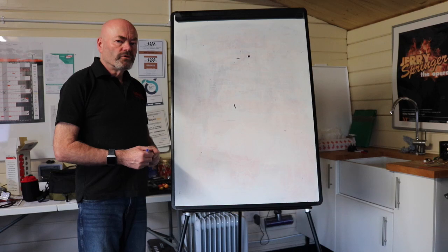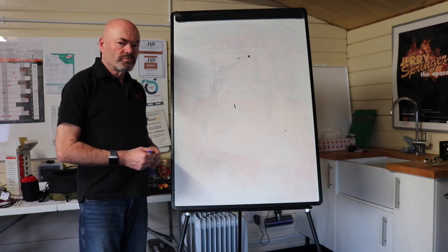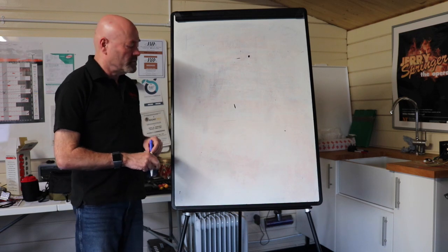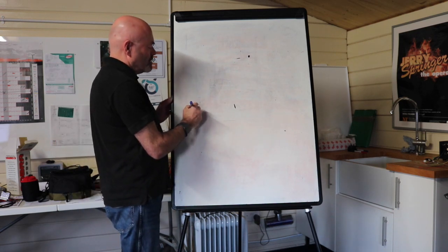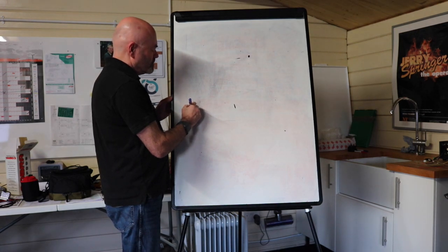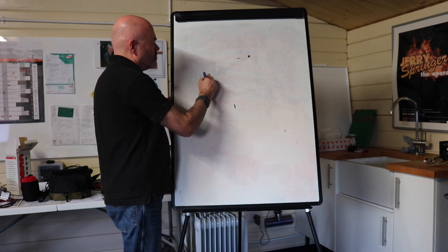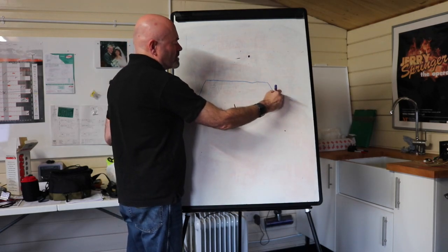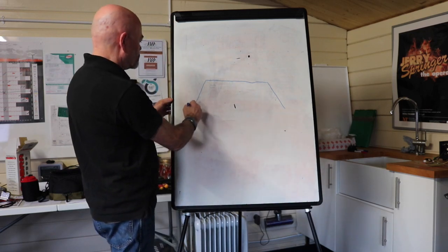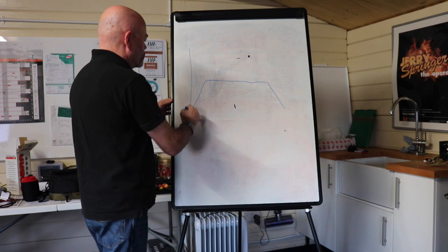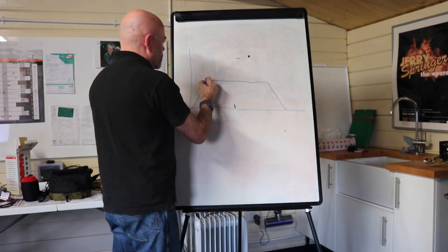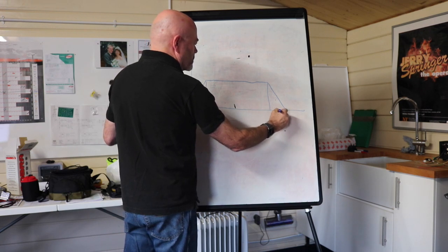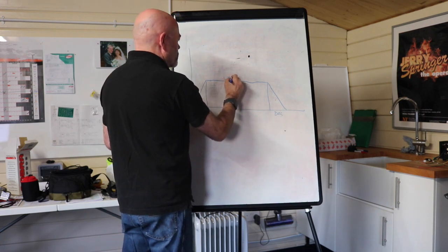As explained on the block diagram, the control system needs to give the information to the variable speed drive as to what to do, direction, speed, but it also needs to give it the acceleration and the deceleration. It does this by giving it a trapezoidal signal. So starting at zero speed, it will accelerate up, reach the speed that it's required to do, travel, then it will decelerate and then it will land at position. You end up with what's called a trapezoidal waveform, where this part is the acceleration, this part is the deceleration, and this is the level speed.